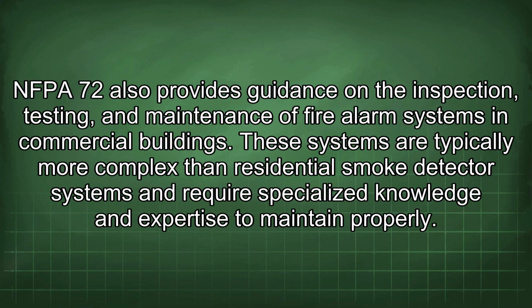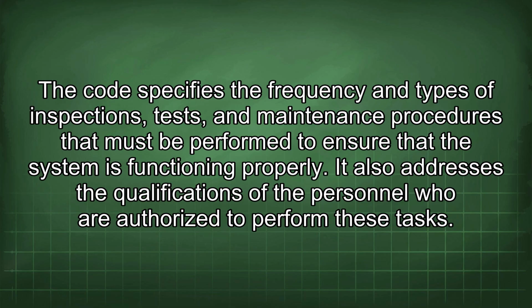NFPA 72 also provides guidance on the inspection, testing, and maintenance of fire alarm systems in commercial buildings. These systems are typically more complex than residential smoke detector systems and require specialized knowledge and expertise to maintain properly. The code specifies the frequency and types of inspections, tests, and maintenance procedures that must be performed to ensure that the system is functioning properly.